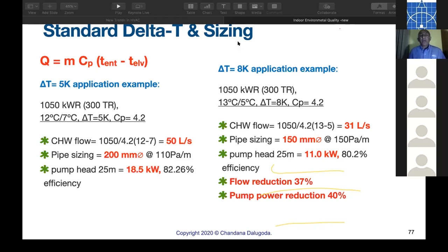But we transform that to an 8K application, same chiller, now operating at 13/5, delta T 8K, CP same. Now the chilled water flow drops to 31. That is a great advantage. Why? Chilled water flow is slow.